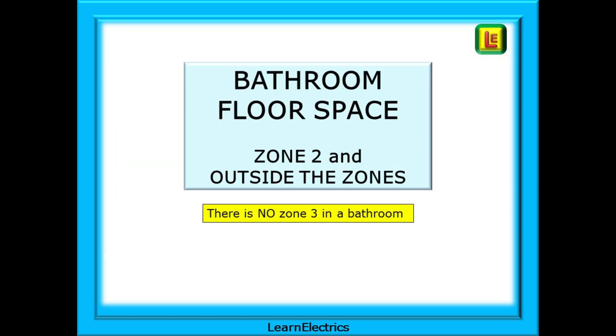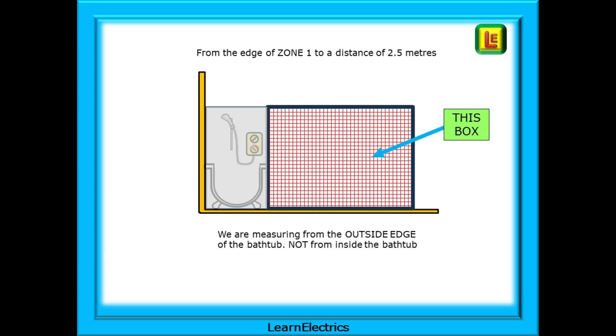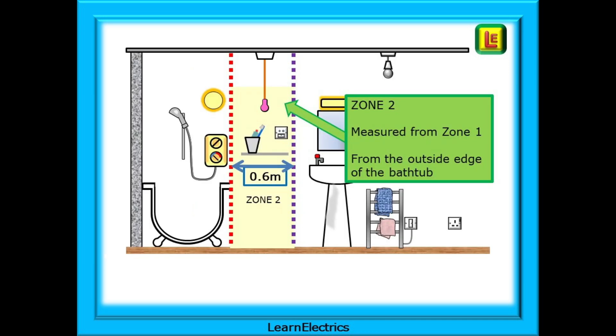Looking at the bathroom floor space: there is no zone 3 in a bathroom — another exam favourite to catch you out. There are two zones, and both start from the outside edge of the bathtub, from the edge of zone 1, not zone 0. This box extends along the floor to a distance of 2.5 meters from zone 1. Zone 2 is the space up to 0.6 meters from the edge of the bath — from the edge of zone 1. Notice there is no mention of zone 0.